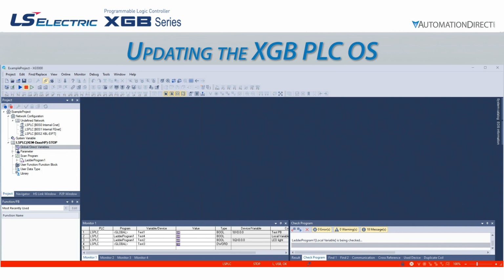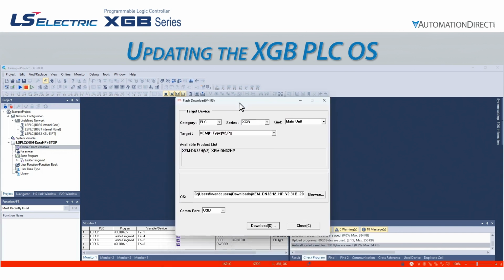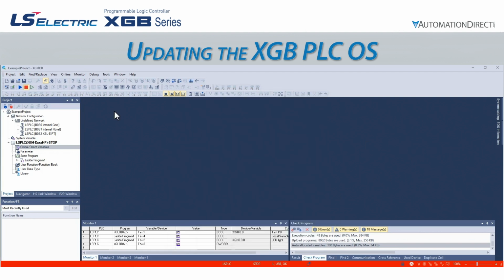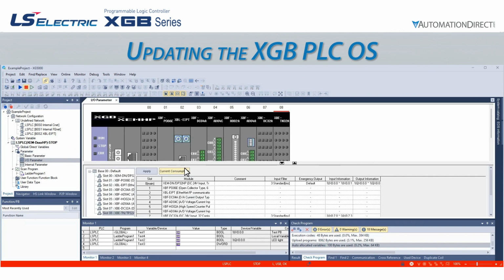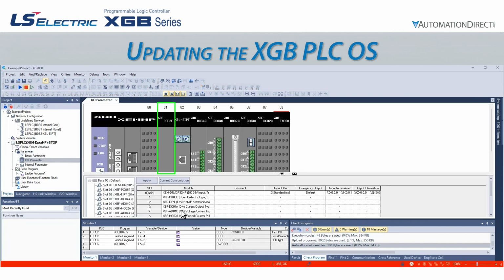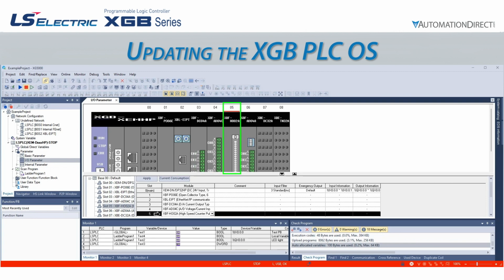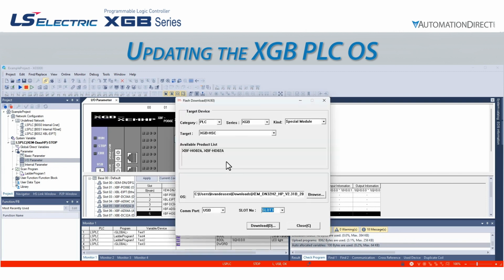Certain non-CPU modules, such as high-speed counters, also use the flash download utility for updating their OS. The process is almost identical, but we will select a different kind, target, and OS to match our module. We will also need to select the correct slot number the module is located at. It is very important this slot number matches the XG5000 slot numbering. Do not just count how many modules are attached. Some CPUs, like ours, use the integrated motion controller as slot 1, so our counter module is in slot 5, even though it is the 4th connected expansion module.